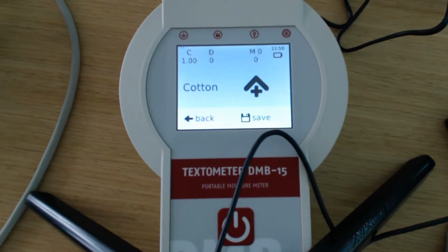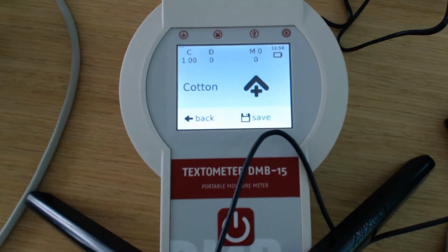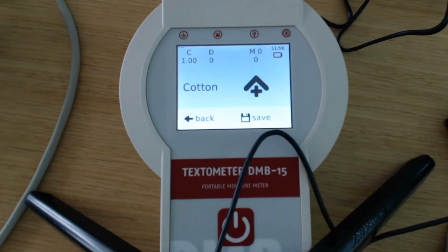What that does is, whenever you put the probe on the fabric, this machine is firing electricity and doing several measurements of the surface resistivity of the fabric and gives you an average. Normally when this happens, it means it's very dry, and whatever you are measuring is on the lower limit of what the instrument can measure.